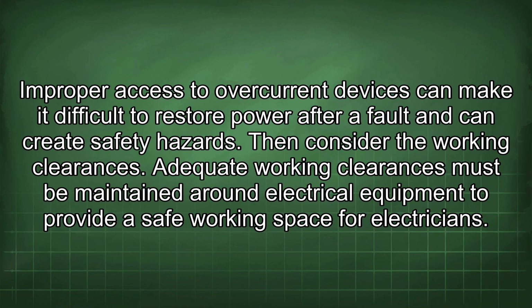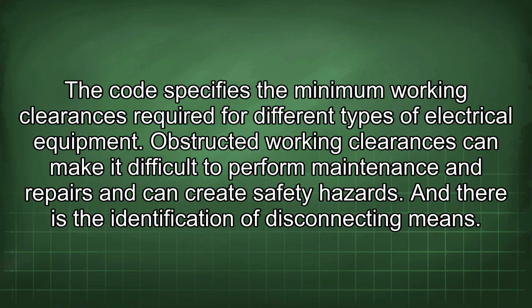Then consider the working clearances. Adequate working clearances must be maintained around electrical equipment to provide a safe working space for electricians. The code specifies the minimum working clearances required for different types of electrical equipment. Obstructed working clearances can make it difficult to perform maintenance and repairs and can create safety hazards.